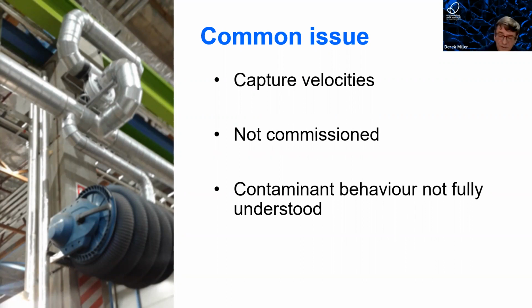And the important thing around the commissioning is, as I say, the only ones I've seen here have been commissioned by the same people that have built it and installed it. That's bad work practice. Commissioning should always be done by another company, as an independent check of your work, as a quality control. And in this case, again, we can see the contaminant's not been considered.